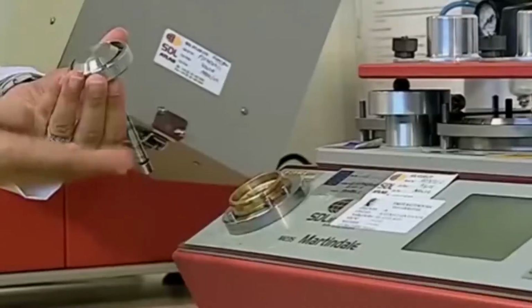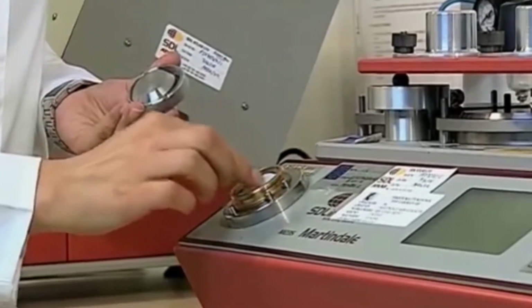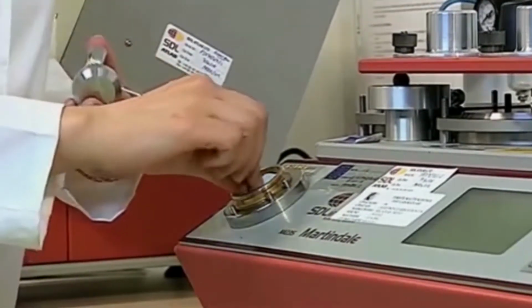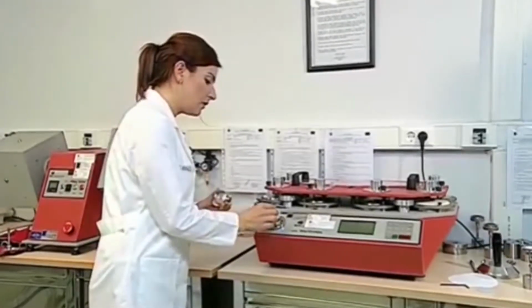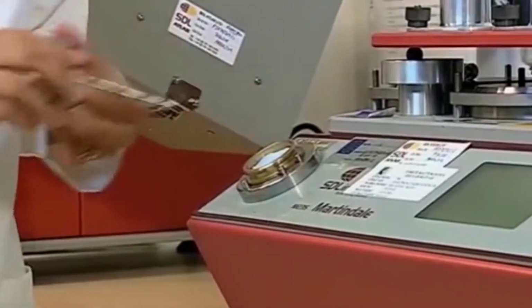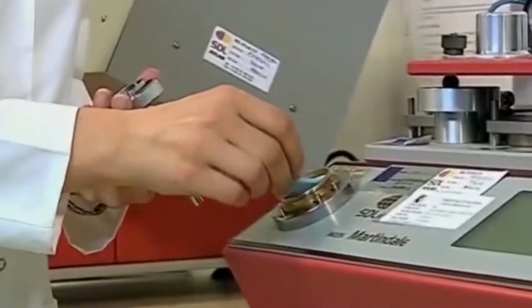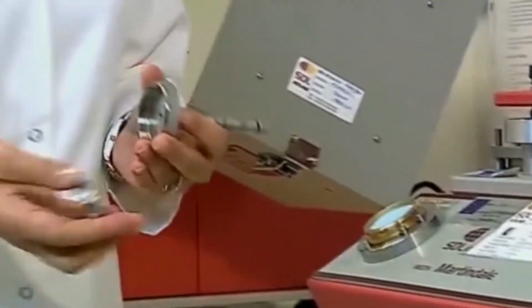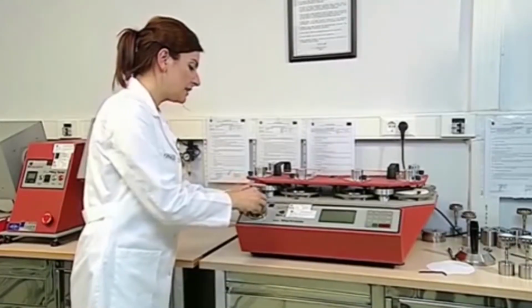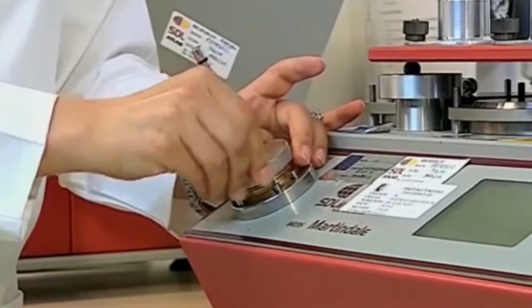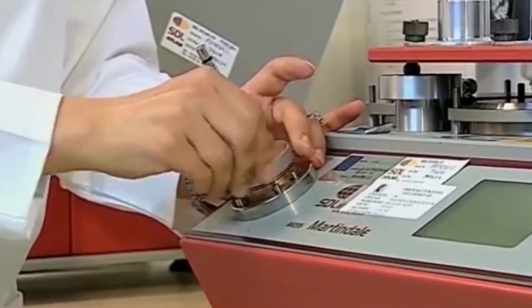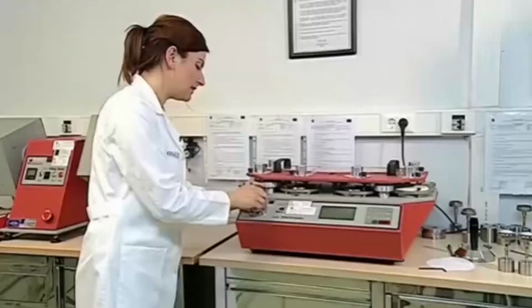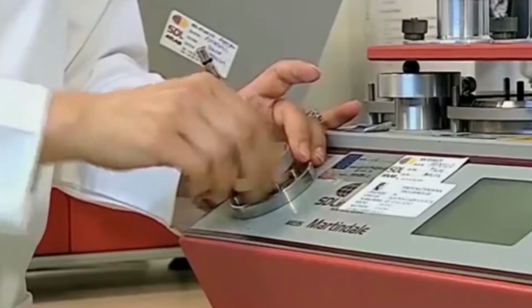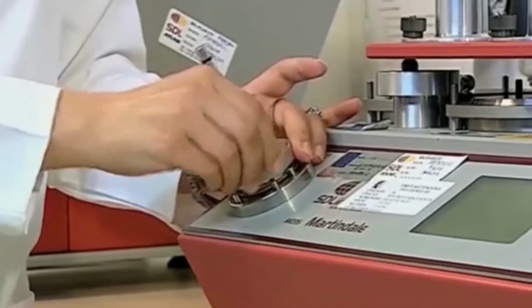The sample in the Martindale abrasion and pilling tester on the table is attached to the holder. The sample is placed into the collar in a way that its front side faces downwards. If the sample is lighter than 500 grams per square meter, foam is inserted. The foam is also cut as 38 millimeters. The device is placed on the foam and the sample holder is compressed. In this way, three pieces of 38 millimeter diameter samples are firmly placed in the sample holder.